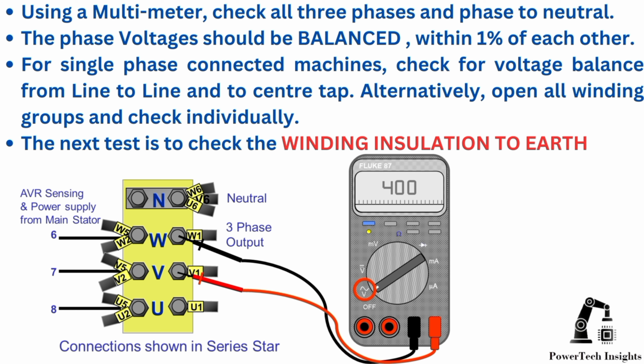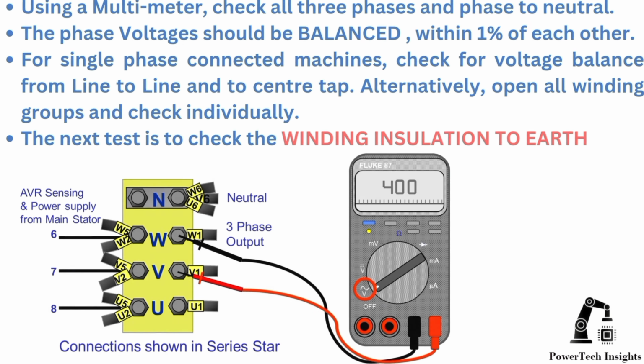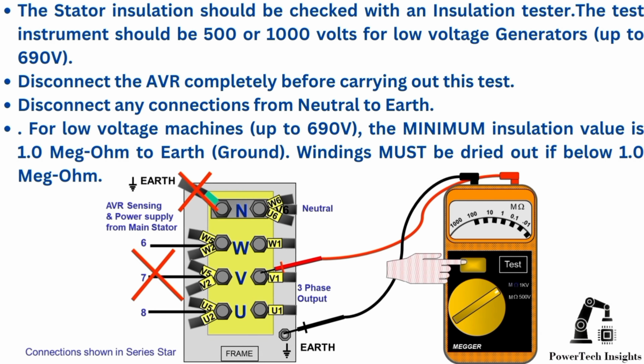The next test is to check the winding insulation to earth. The stator insulation should be checked with an insulation tester. The test instrument should be 500 or 1000 volts for low voltage generators. Disconnect the AVR completely before carrying out this test. Disconnect any connections from neutral to earth. For low voltage machines, up to 690V, the minimum insulation value is 1.0 megohm to earth or ground. Windings must be dried out if below 1.0 megohm.